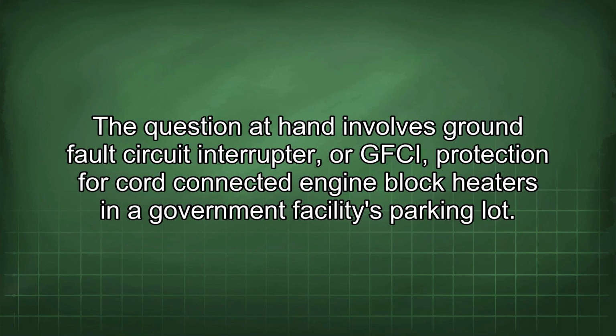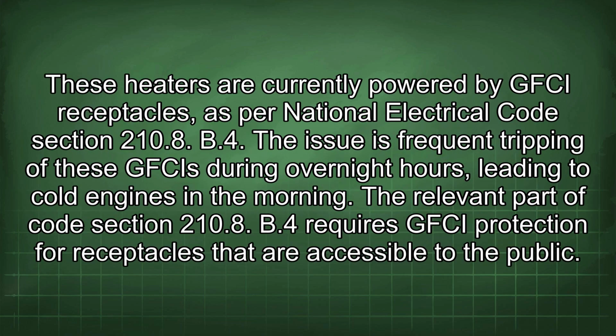The question at hand involves ground fault circuit interrupter, or GFCI, protection for cord-connected engine block heaters in a government facility's parking lot. These heaters are currently powered by GFCI receptacles as per National Electrical Code Section 210.8 B4. The issue is frequent tripping of these GFCIs during overnight hours, leading to cold engines in the morning.